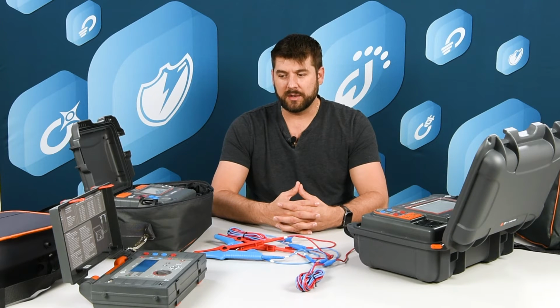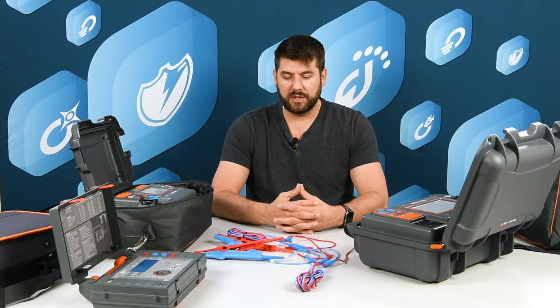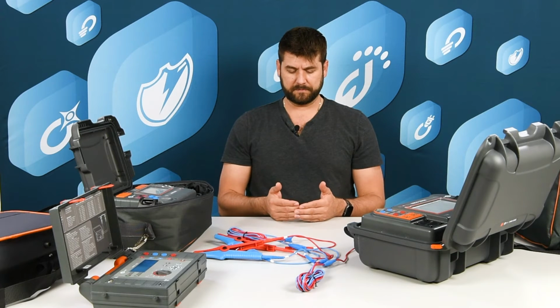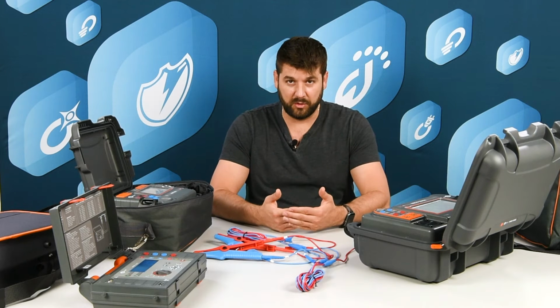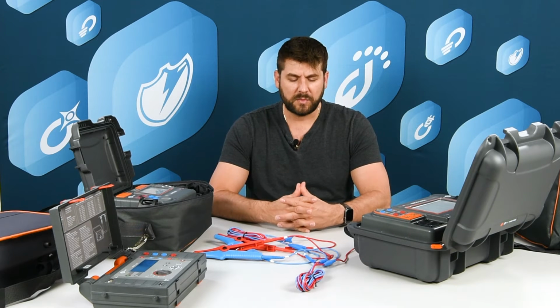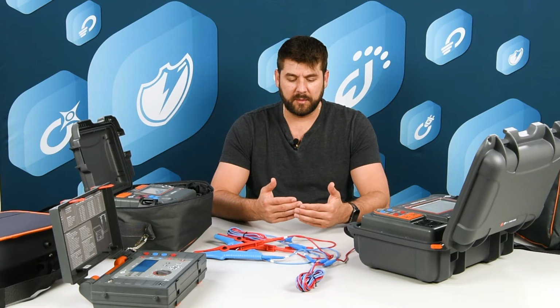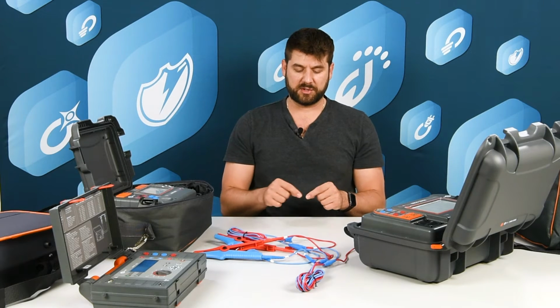But if you were talking about a connection that's going to be handling hundreds of amps, or even thousands of amps in some cases, you're going to need to have a resistance level in the microohms. Like, for example, through a circuit breaker, you want to have like 50 microohms or 100 microohms, and they even get down to like 6 microohms for some of the very high quality, high current circuit breakers.